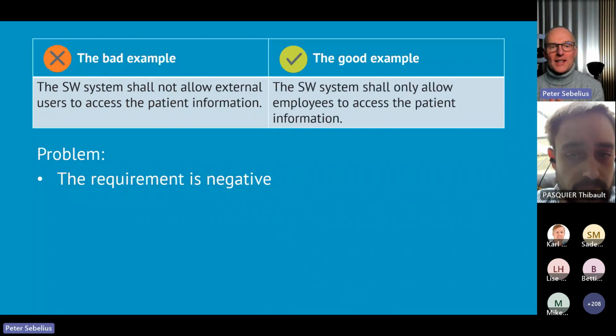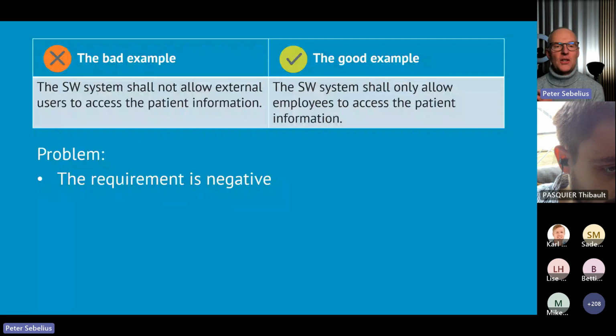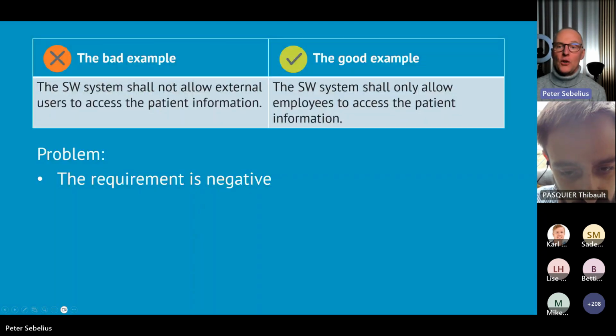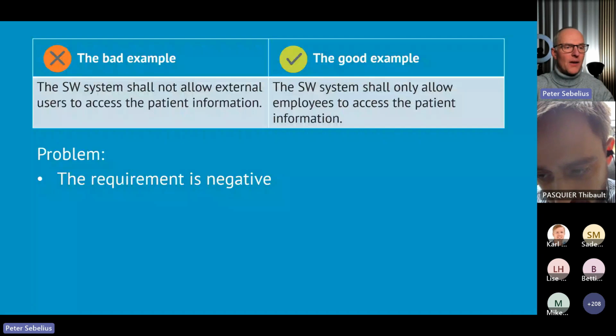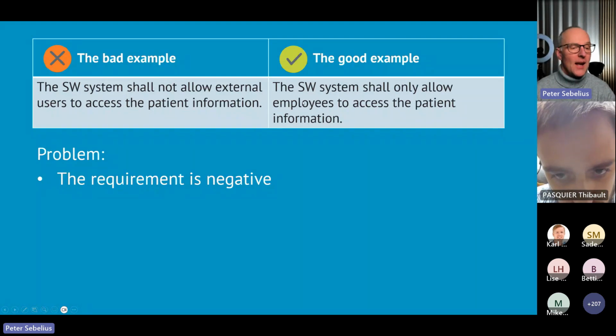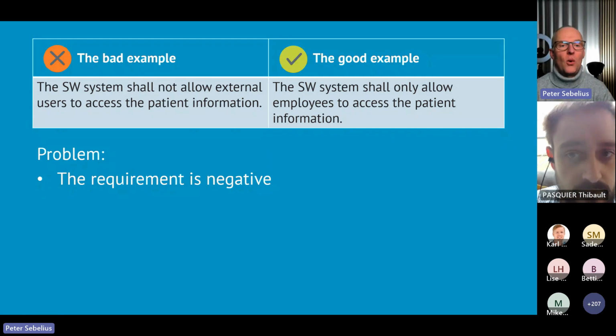The way you should improve this negative requirement is to say that the software system shall only allow employees to access the patient information. And this is an improvement, because in the previous bad example you are excluding just one category, right? External users from accessing the patient information. But in theory, there could be a huge number of other groups, which means you're just preventing one group from accessing the patient information. In the good example, we turned it around and said there is only one group that should have access, and every other group is excluded, which makes it a whole lot less ambiguous. So you should turn it around this way. That's definitely the way to go.